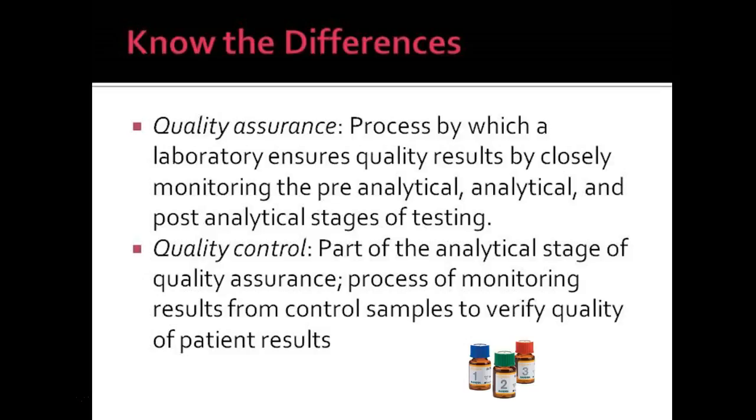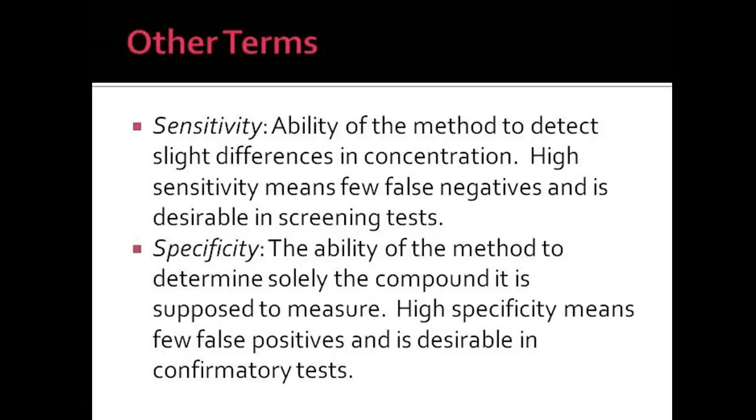If we're not getting the answers that we should get with each of these QC vials, then we cannot report patient results, and we have to refer to the owner's manual or things like that with our analyzer to figure out why it's not coming in range and how we can fix it.